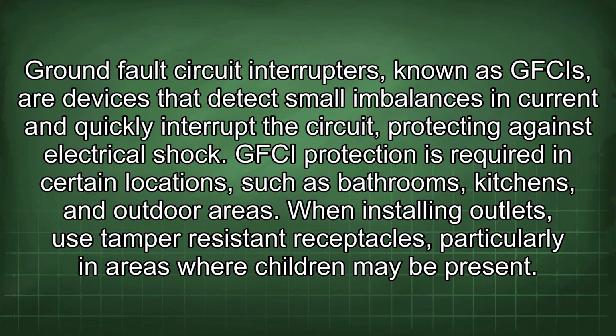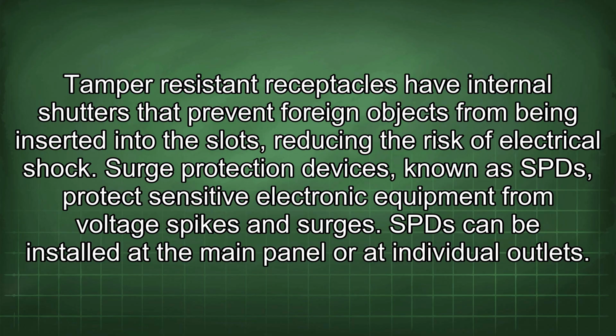When installing outlets, use tamper-resistant receptacles, particularly in areas where children may be present. Tamper-resistant receptacles have internal shutters that prevent foreign objects from being inserted into the slots, reducing the risk of electrical shock. Surge protection devices, known as SPD, protect sensitive electronic equipment from voltage spikes and surges. SPD can be installed at the main panel or at individual outlets.